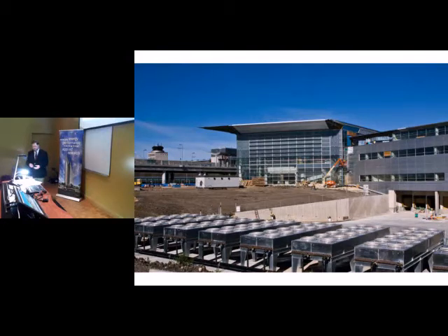So again, it speaks to the efficiency of the systems that were installed and how well they worked, and exceeding our expectations. What we found in some areas is that the radiant floors actually serve as the primary means of heat, that we can set a baseline of heating for the building using the radiant floor, setting it at a particular temperature, just leaving it there, and then trimming the temperature of the space by adjusting the air temperature on the air handlers. And what that ends up doing is it's saving a huge amount of energy from the central utilities plant, because we're using a very, very efficient way to get temperature into the space with low intensity heat, so we don't need a lot of energy to do that. And we also reduce the amount of effort the fans and fan systems have to put into heating the air in the building itself. So that's worked out very, very well in terms of the efficiency side.